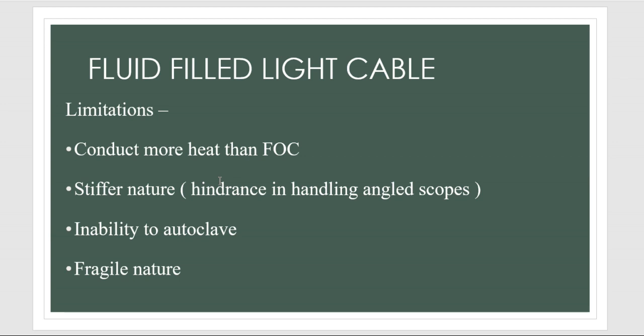Another important limitation of the fluid-filled light cable is that we cannot autoclave it, whereas with the fiber optic cable we can. The fluid-filled cable is also of a very fragile nature compared to the fiber optic cable. Due to these limitations and the availability of fiber optic cable, fluid-filled light cables are not commonly used nowadays, and the better choice is always the fiber optic cable.